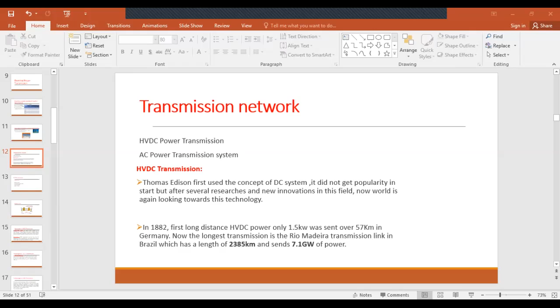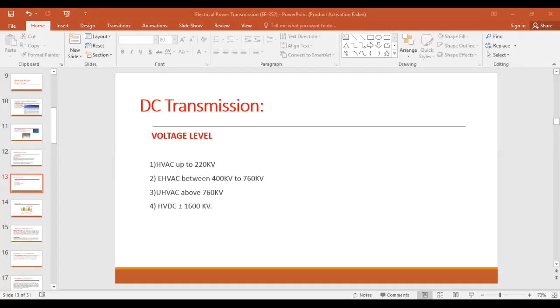Okay, now moving on, we have some voltage levels in the transmission system. We know that we generate at 11 kV, but we transmit at the high voltage of 132 or 220 kV, and then we have the extra high voltage between 400 and 760 kV, then ultra high voltage AC. These are the AC voltage levels above 760 kV. And last but not least, we have the high voltage DC of plus or minus 1600 kilovolt, which we could transmit on the transmission line.